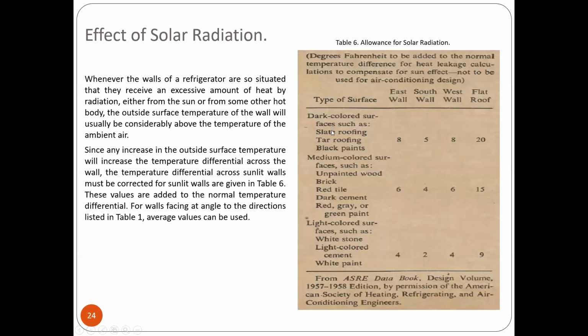So now, effect of solar radiation. So when the walls of a refrigerator are so situated that they receive an excessive amount of heat by radiation, na kapag sa araw o sa labas mo nilagay, either from the sun or from some other hot body, the outside surface temperature of the wall will usually be considerably above the temperature of the ambient air. Since any increase in the outside surface temperature will increase the temperature differential across the wall, the temperature differential across sunlit walls must be corrected for sunlit walls given in table 6.